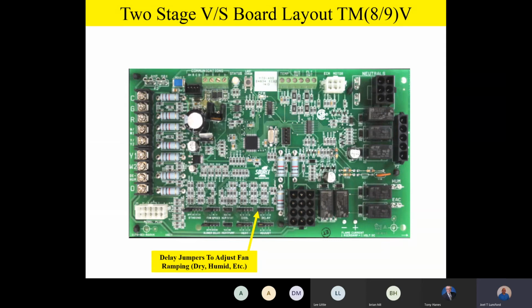So this delay jumper is pretty unique to our variable speed products. This delay jumper is going to allow you to adjust the fan based on your geography. Now, what I mean by that is this: if you have a humid environment or a dry environment like out in the desert, or a temperate environment like we maybe would find in Kentucky or Tennessee or South Dakota, that type of thing. This delay jumper allows you to build in a delay for the indoor fan in the cooling mode. So to give an example, on the B selection, that's the humid selection like we have down here in Alabama, where I'm living.